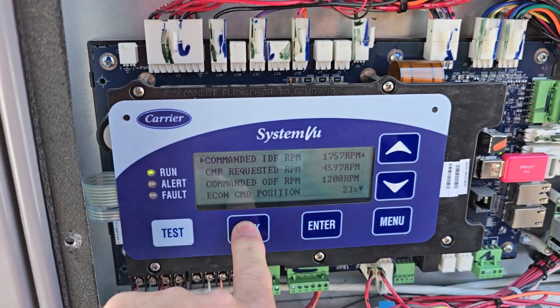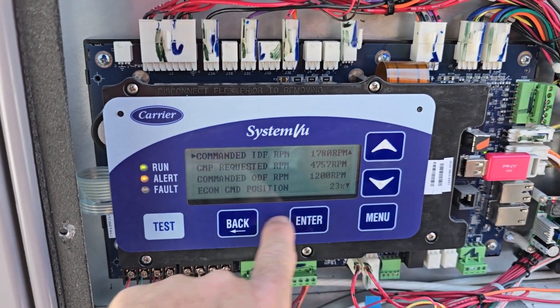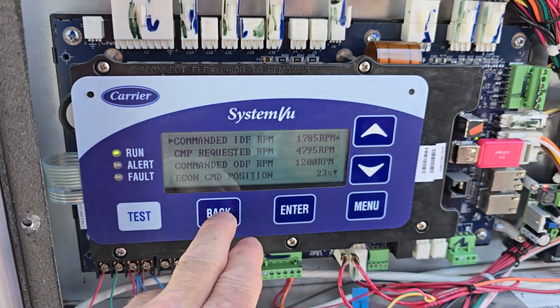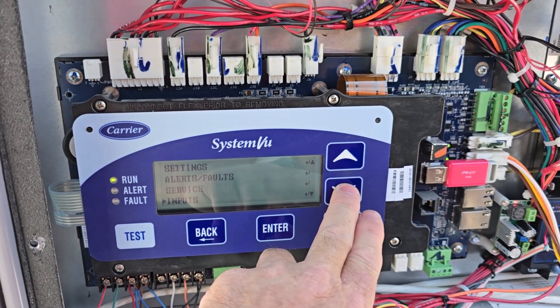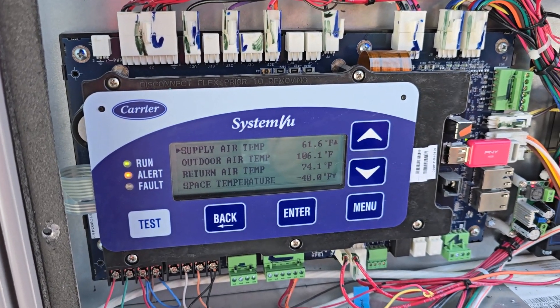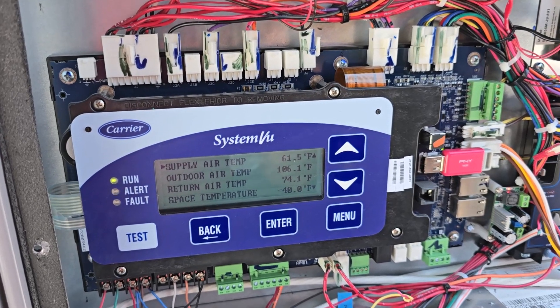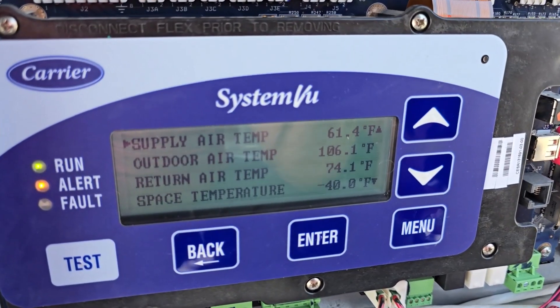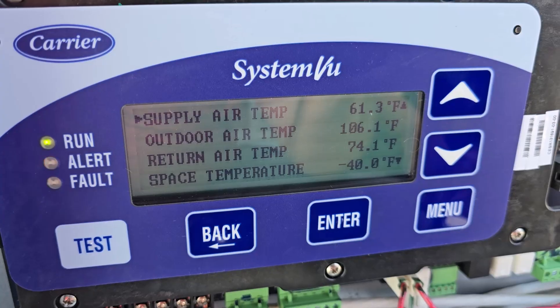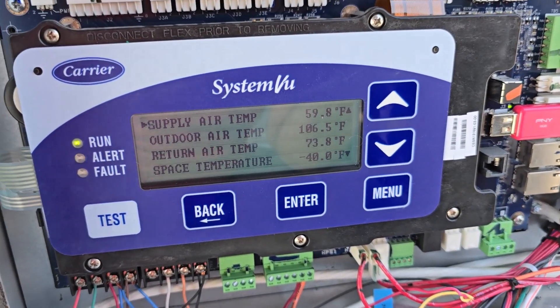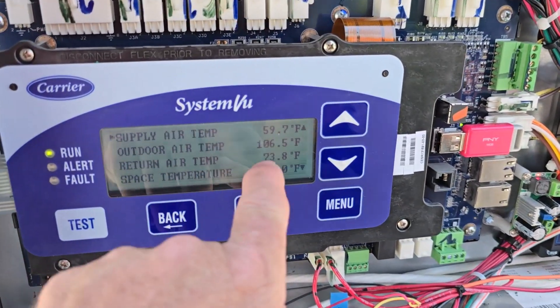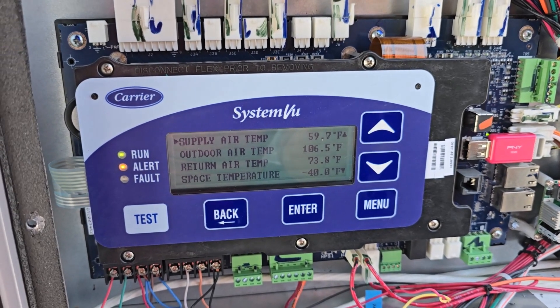So let's go back up to the run status here. Cool. See if it says mode. It is mechanical cooling high cool. So it's ramping up now. 4700, 4800. So if we go back to the inputs, temperatures. This should start dropping. 61.6 there. So it's not quite a 20 degree split. 61.4. So it's dropping. It'll probably get down into the 50s here momentarily. 61. So a minute later it's at 59 degrees and dropping. Inverter temp is now 113. That's not too bad given the temperature outside. 106.5. Return air is starting to drop. It's down to 73.8.